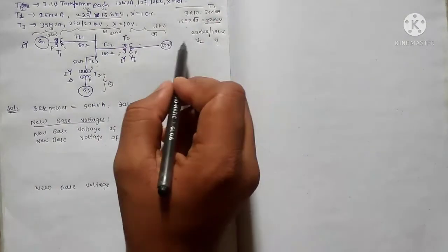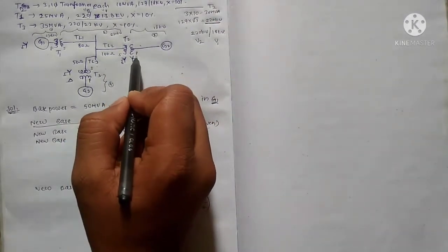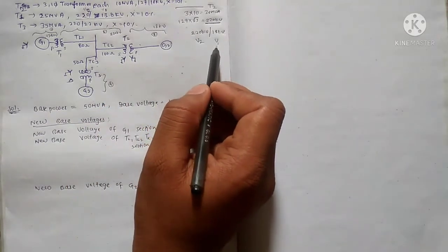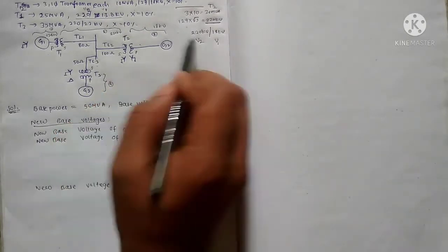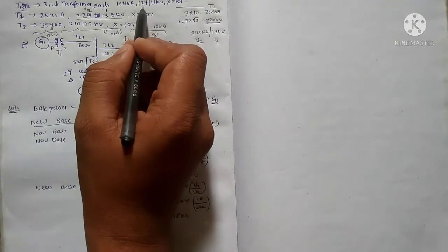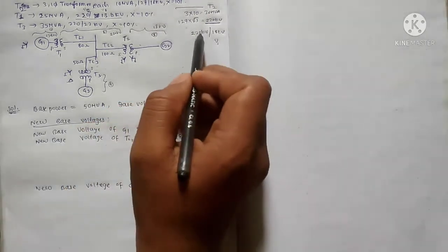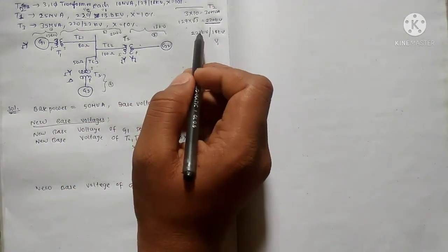Now let's see, this is primary, this is secondary, both are connected in star. Because the primary voltage is 18 kilovolt connected in star, we don't worry about the primary, whatever the connection type, we just ignore it. We just concentrate on the secondary type. Secondary is connected to 127 kilovolt. Secondary is connected to star. Star means the voltage differs, therefore we multiplied by root 3. That's all.